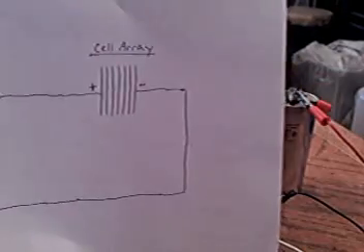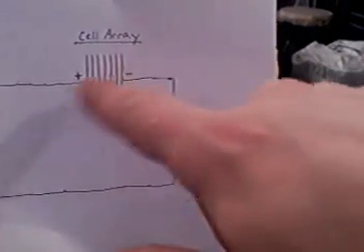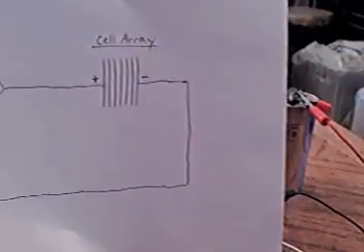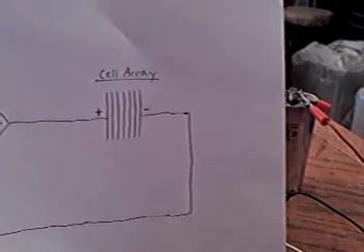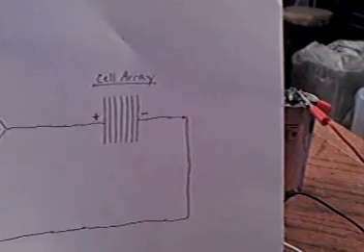So in effect you have 110 across this whole 7 plate array, which is actually 6 cells. That amounts to 110 volts divided by 6. The whole cell array has 110 volts across it. But each chamber only has 110 divided by 6, which is like maybe 18 volts. Each cell has about 18 something volts across it. And that is the beauty of the series cell.